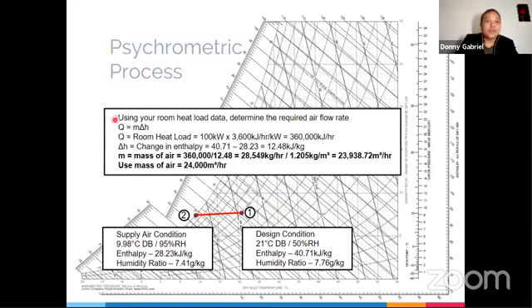degrees. Okay. So using our formula, Q is equal to M delta H. M is the one that we're looking for. Q is the one that's equal to the room heat load. H is the change in enthalpy. So at point 1, the enthalpy is 40.71. At point 2, the enthalpy is 28.23. The change in enthalpy, you remember our enthalpy unit is kilojoule per kilogram. If we know the heat load or the energy needed, the kilojoule, we can convert it into kilowatts. We know it's 100 kilowatts.